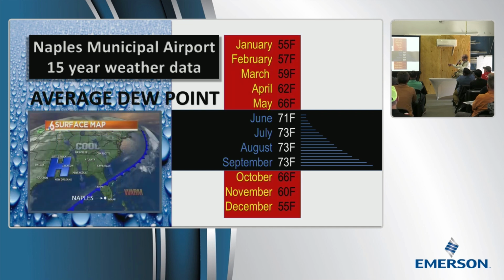Now, this is the time of year when we get these fronts from up north, when the polar vortex pushes down some nice dry weather from outdoors. And if you have sweating duct and sweating air handler problems for this part of the year, you will probably find something that's wrong. What we find is that for systems that are set up well commissioned, they're running reasonable static pressures, they're running the anticipated flow rates. What we see with those is that they work pretty good until you get into that rainy season.